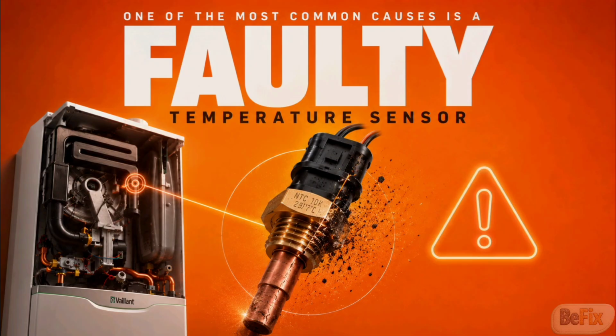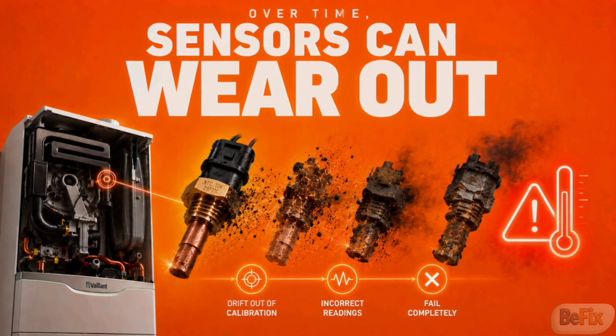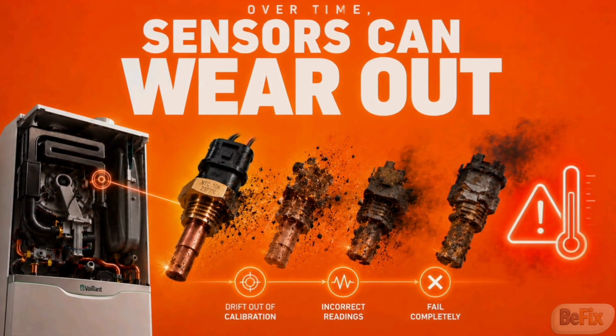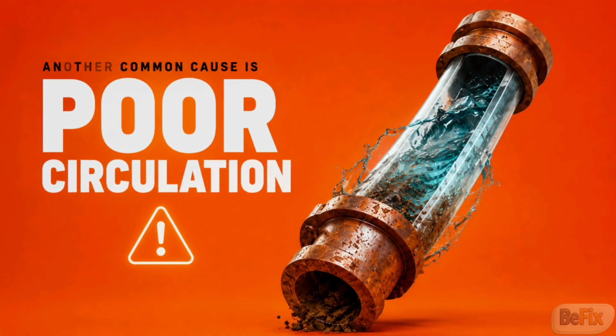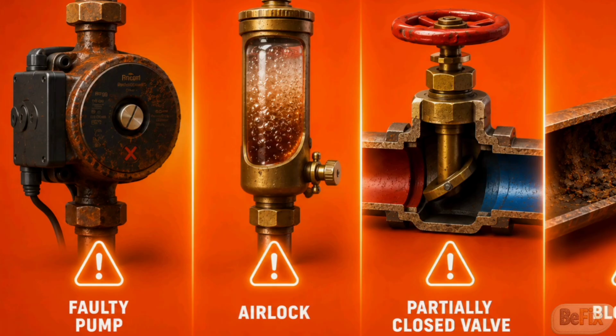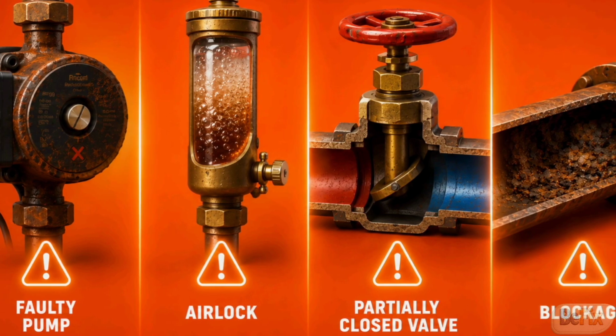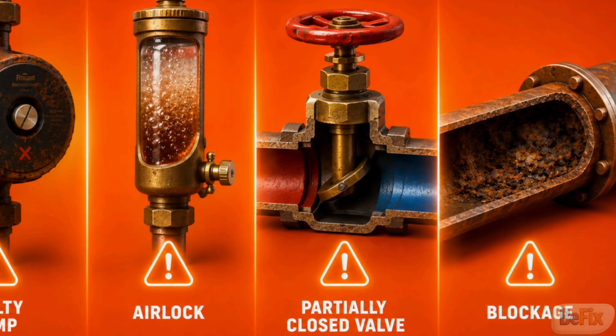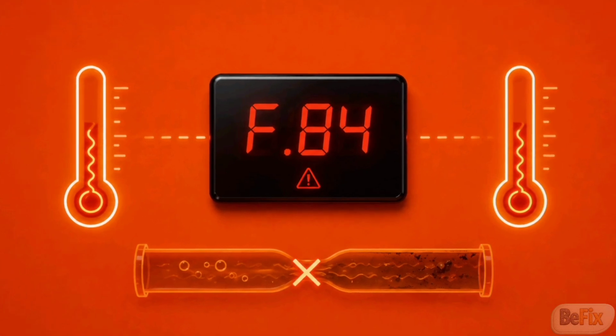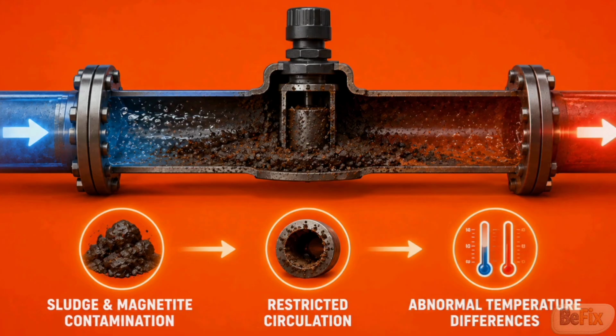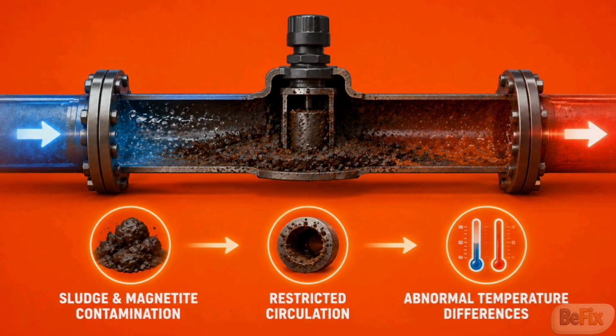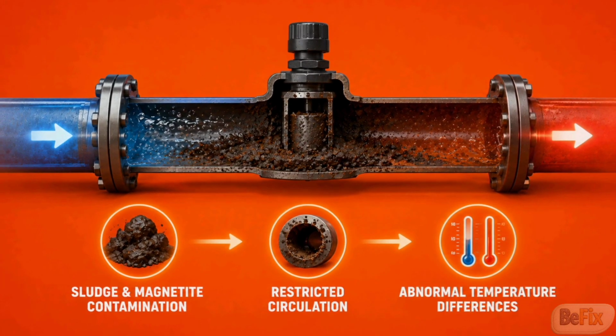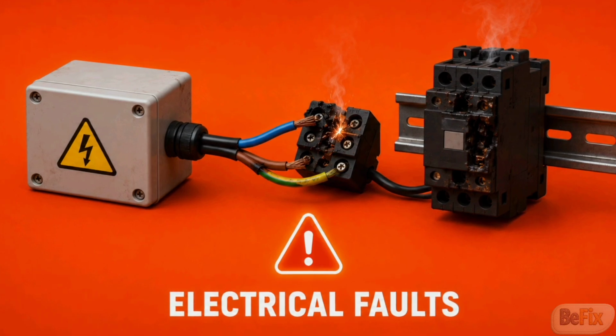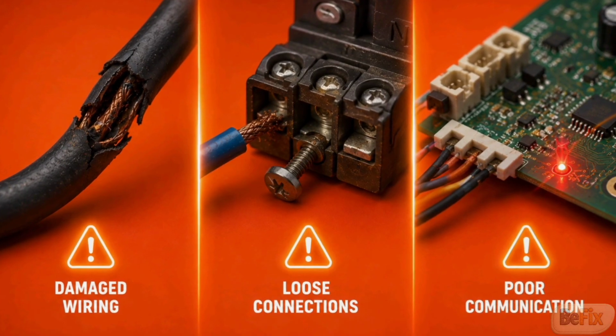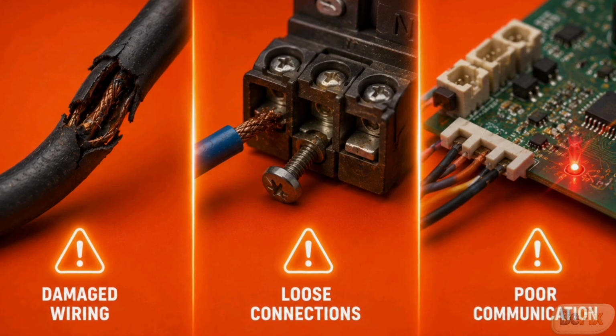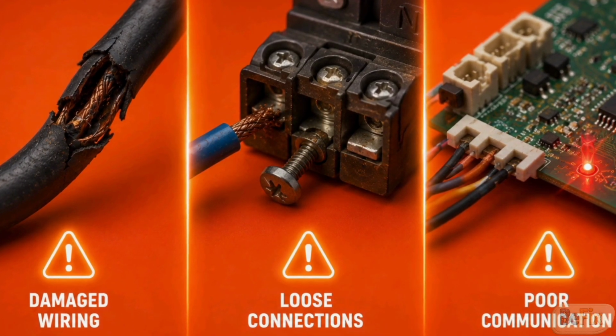One of the most common causes is a faulty temperature sensor. Over time, sensors can wear out, drift out of calibration, or fail completely, causing incorrect readings. Another common cause is poor circulation. If water cannot move properly through the system due to a faulty pump, airlock, partially closed valve, or blockage, the temperature readings can become unstable and trigger an F.84 fault. Sludge and magnetite contamination can also restrict circulation and create abnormal temperature differences throughout the system. Electrical faults are another possibility. Damaged wiring, loose connections, or poor communication between the sensors and the boiler's PCB can result in inaccurate temperature readings.